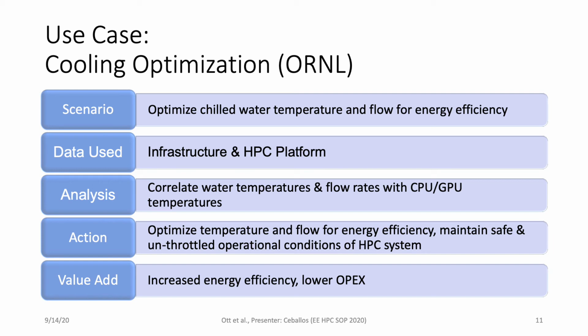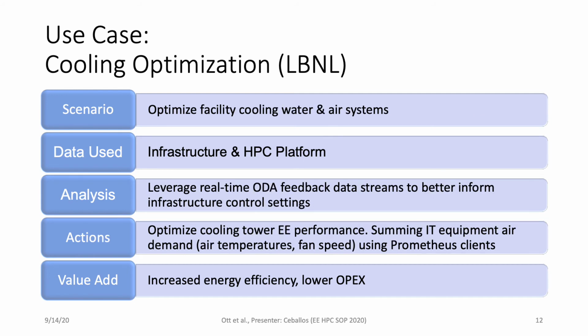Facility engineers are given access to a holistic view that has the mechanical and environmental data from the central energy plant, as well as the power and thermal data from all GPUs and CPUs. With this view, the delta temperature between supply and return is maintained high, but in a way that the GPU and CPU temperatures are kept just under the threshold of throttling to help ORNL increase the amount of free cooling they can utilize, even on days with adverse wet bulb temperatures, and thus improve the site's energy efficiency and OPEX.